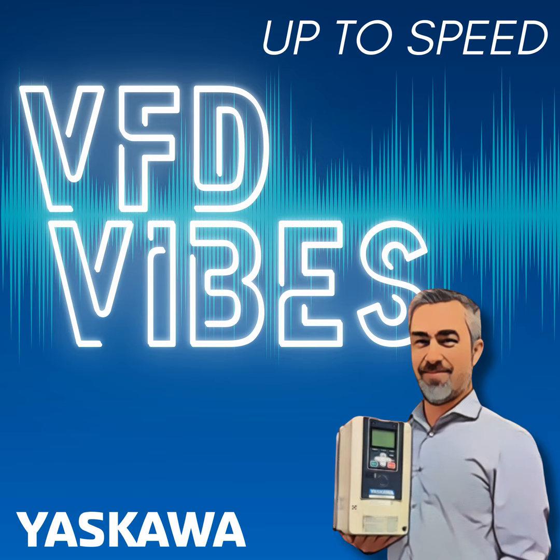You might think that the VFD has a voltage monitor on the front end. That's not the case. The Yaskawa VFD or HV600, some of the other drives like Z1000 and such, monitor the DC bus, and they monitor the voltage on the DC bus and what we call DC bus ripple. If you have three-phase applied to the input power of the drive, we're running a three-phase motor, probably everything's running normal and there's no issue.